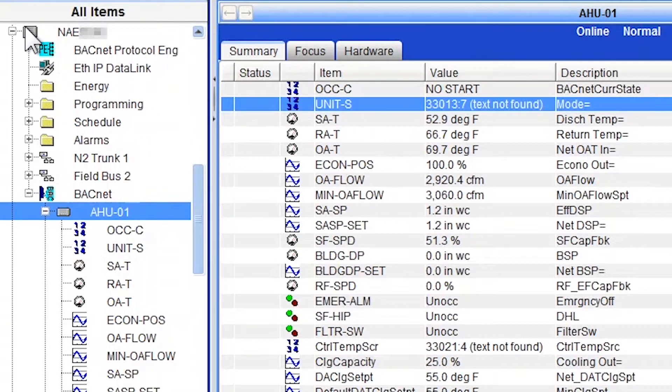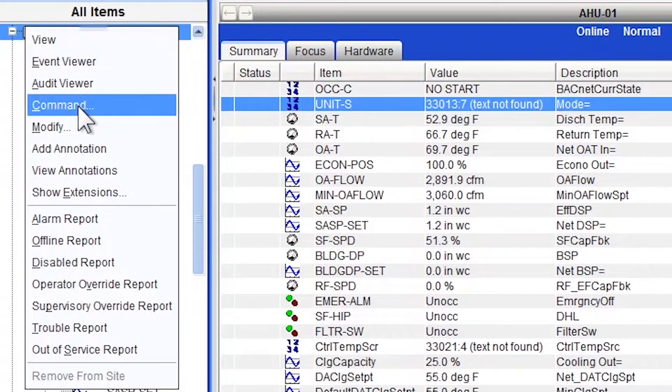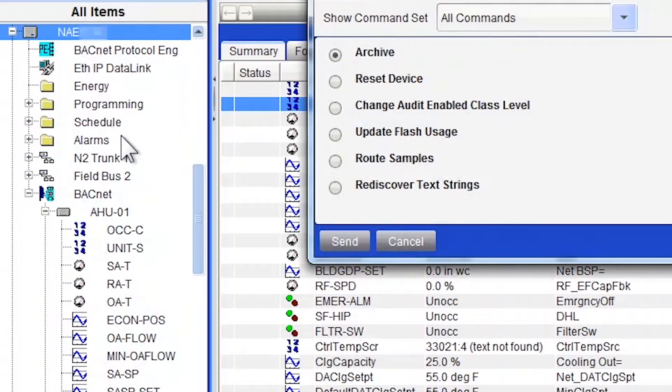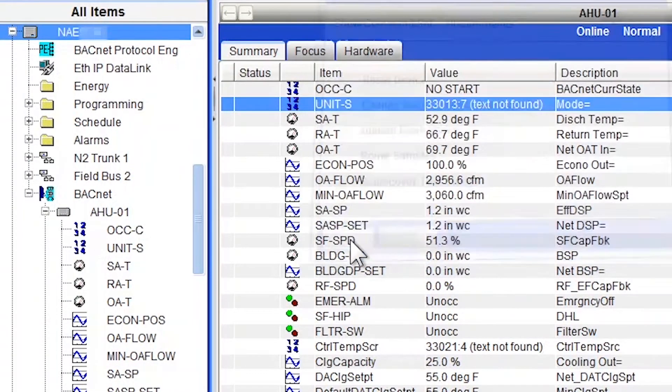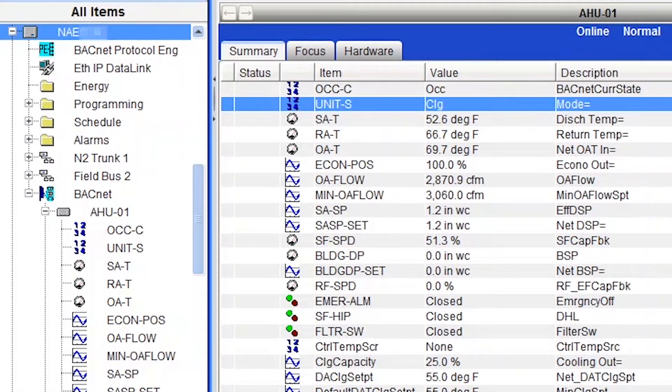Now you know the trick. Right click on your NAE, Command, Rediscover Text Strings, and send the command. And you'll see. And everything got fixed.